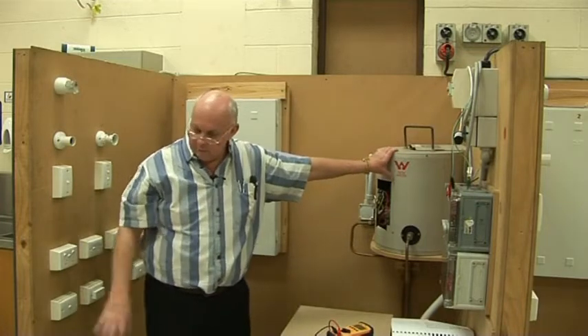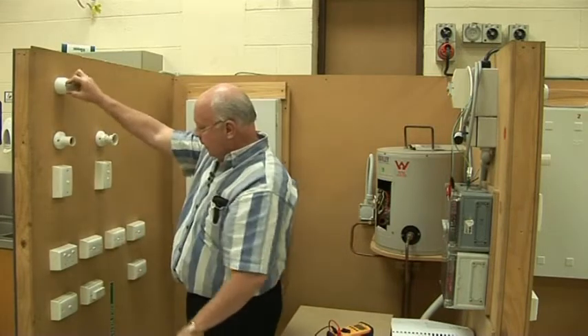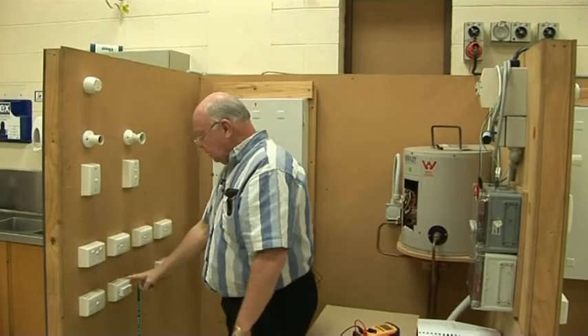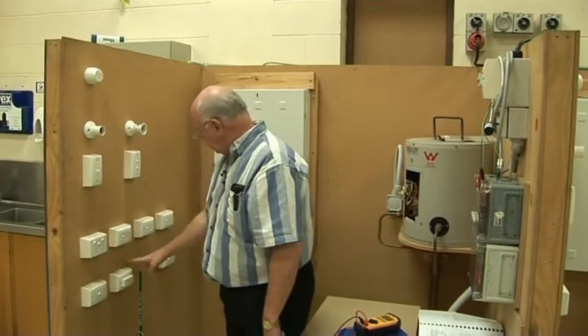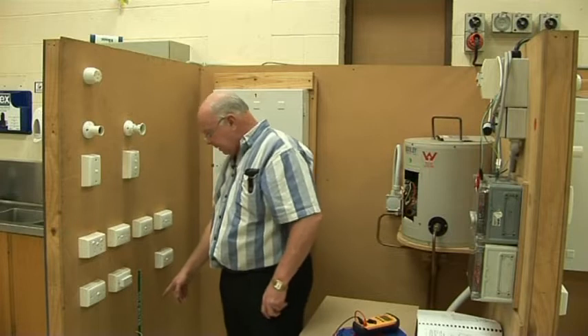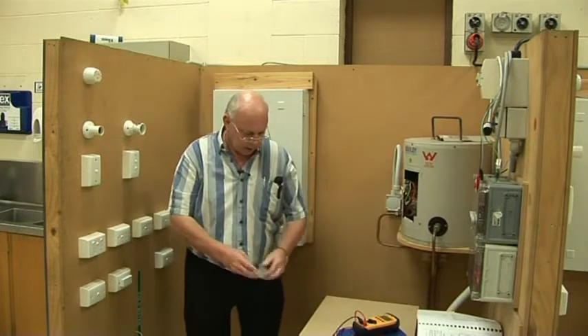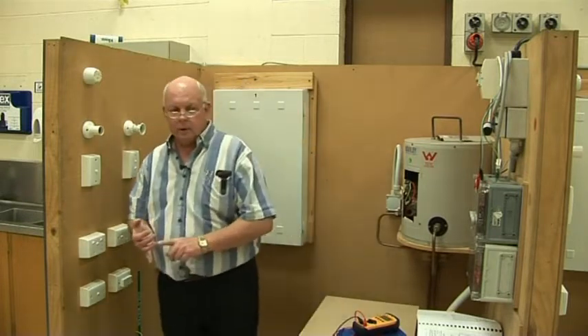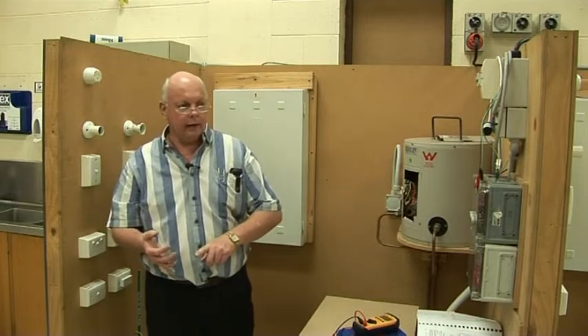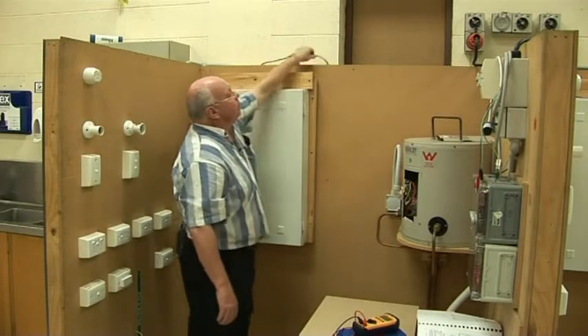Obviously the hot water service here is part of this installation. We've got socket outlets, two light circuits, there's an extraction fan here, our range plug there and a 15 amp one there as well. Main earth, water pump coming in, and they've got all the bonding together from the hot water service. I'm not going to do live/dead testing now — that's not part of this. So let's assume we've done our dead testing and visual inspection. This is just the electrical testing part. How do I know it's dead?